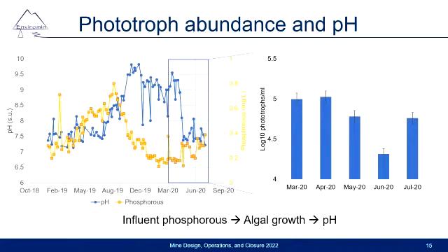The big take home here, though, is just some optimization, not going overboard, and keeping an eye on nutrients can keep a pond like this healthy. It allows them to continue to use it for land discharge without having to treat with sulfuric acid. No need for algicides in the system, so long as they are keeping an eye on their microbial population and just keeping some general tabs on it. And with the good group that's out there that is keeping good close tabs on what's happening, that's exactly what they've got going on right now.